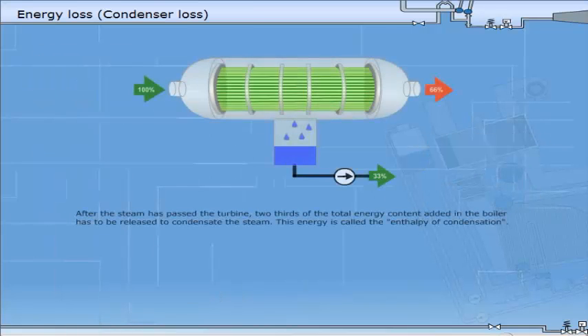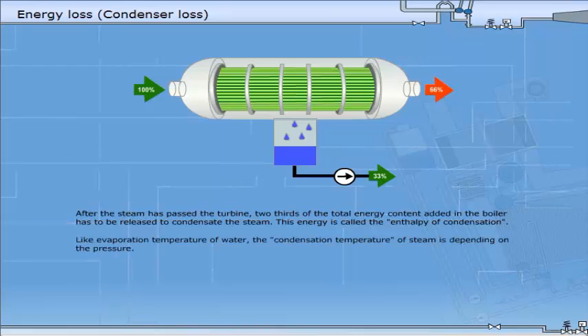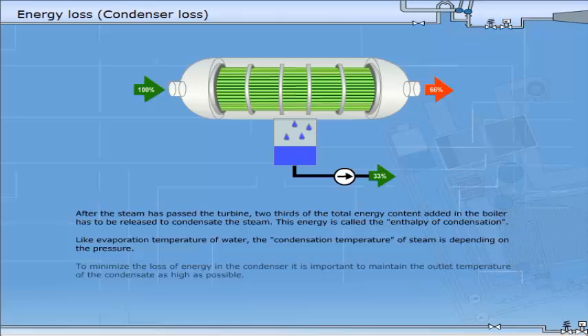After the steam has passed the turbine, two-thirds of the total energy content added in the boiler has to be released to condensate the steam. This energy is called the enthalpy of condensation. Like evaporation temperature of water, the condensation temperature of steam is dependent on the pressure. To minimise the loss of energy in the condenser, it is important to maintain the outlet temperature of the condensate as high as possible.